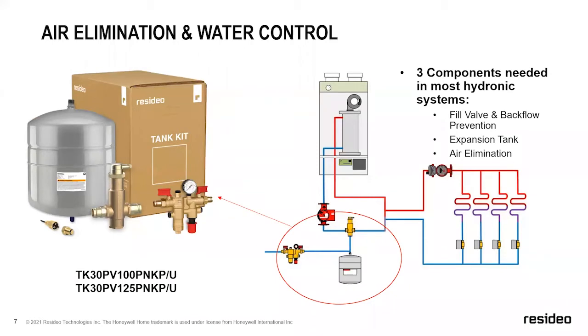And the one exception I'll put on that is those of you that are using glycol for a glycol-based system, you won't use a fill valve and backflow. So you'll use a glycol feed system of some sort, but that's kind of the one exception. Other than glycol systems, this is pretty much the way it's done. The 3 components you have to have with virtually every boiler.